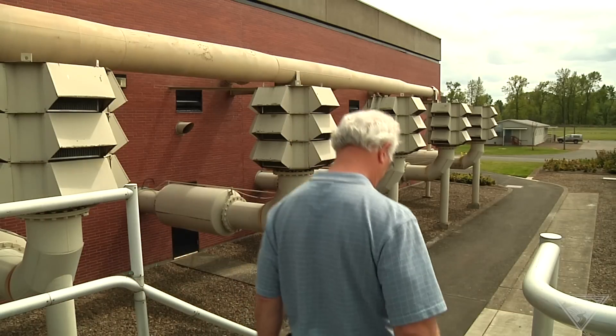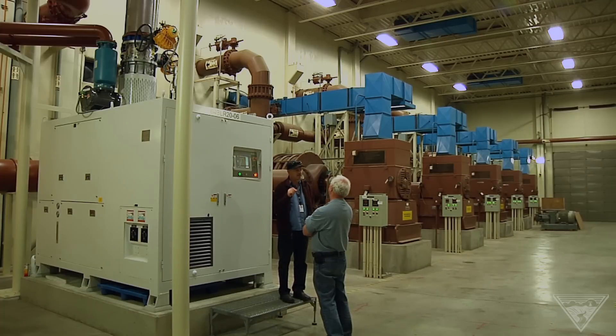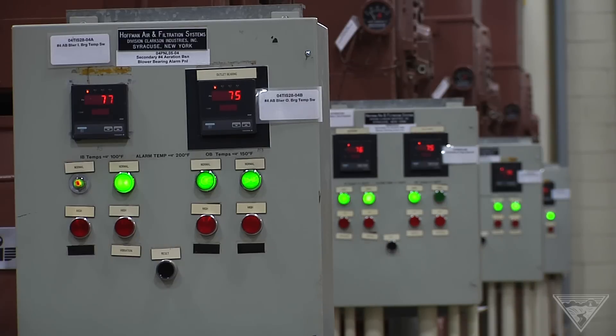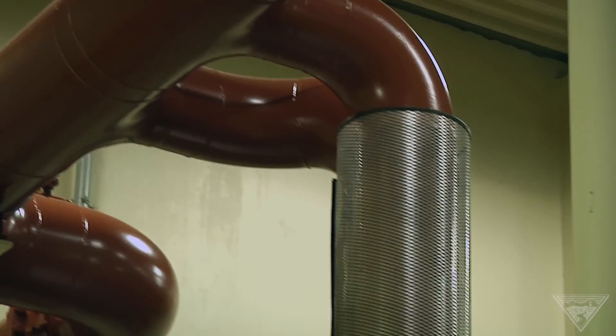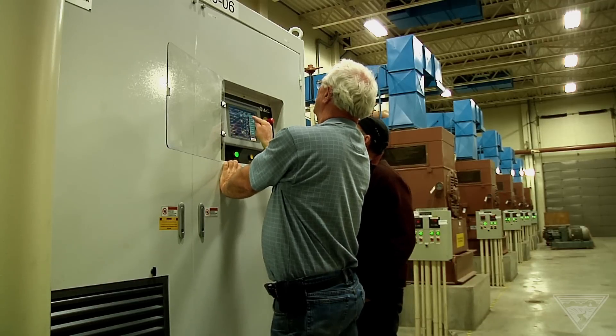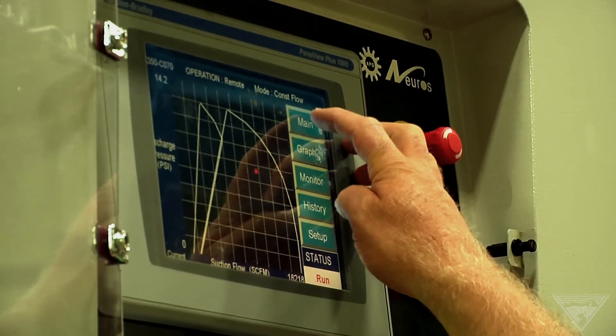It uses about 50 to 60% of our power here on site. As part of a recent project with Eugene Water and Electric Board and Bonneville Power Administration, the Metropolitan Wastewater Management Commission upgraded the facility's blower system. These blowers have two cores, so you can ride up and down the power curve and get the appropriate flows, whereas older units are more of an on-off kind of thing — 1,000 horsepower at a given flow rate and pressure, or nothing. This gives better functionality and, as a demand-response tool, visibility and controllability we didn't have before.